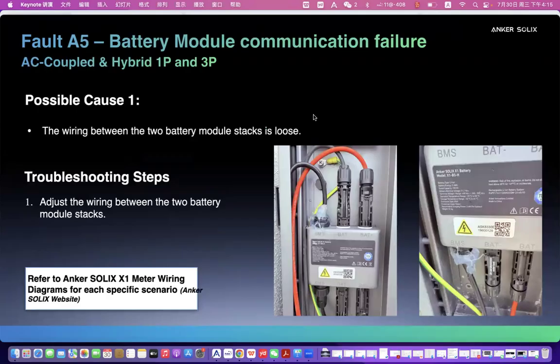Next is A5. What does this mean? It means battery module communication failure. At this time, we just focus on our inverter's left side and the battery. It has the DC cable wiring. Make sure everything is tight, not loose. If something is loose, it will show this error and you will lose some batteries. You cannot find them when you refresh the machine. For example, if you have 4 batteries and something has a loose connection, you will only find 2 batteries, or 1 battery or 3 batteries. You can't find everything. So make sure, because it's really easy to connect. Just plug in, it's really easy to operate.